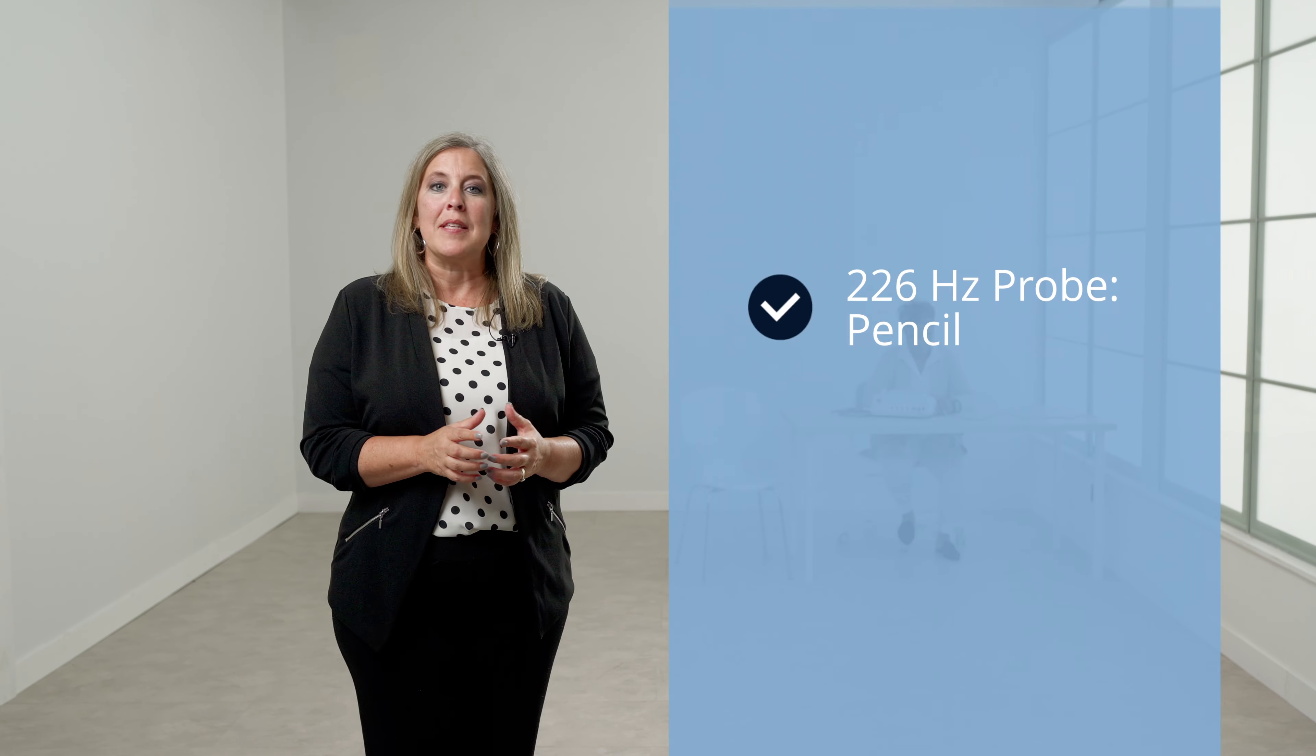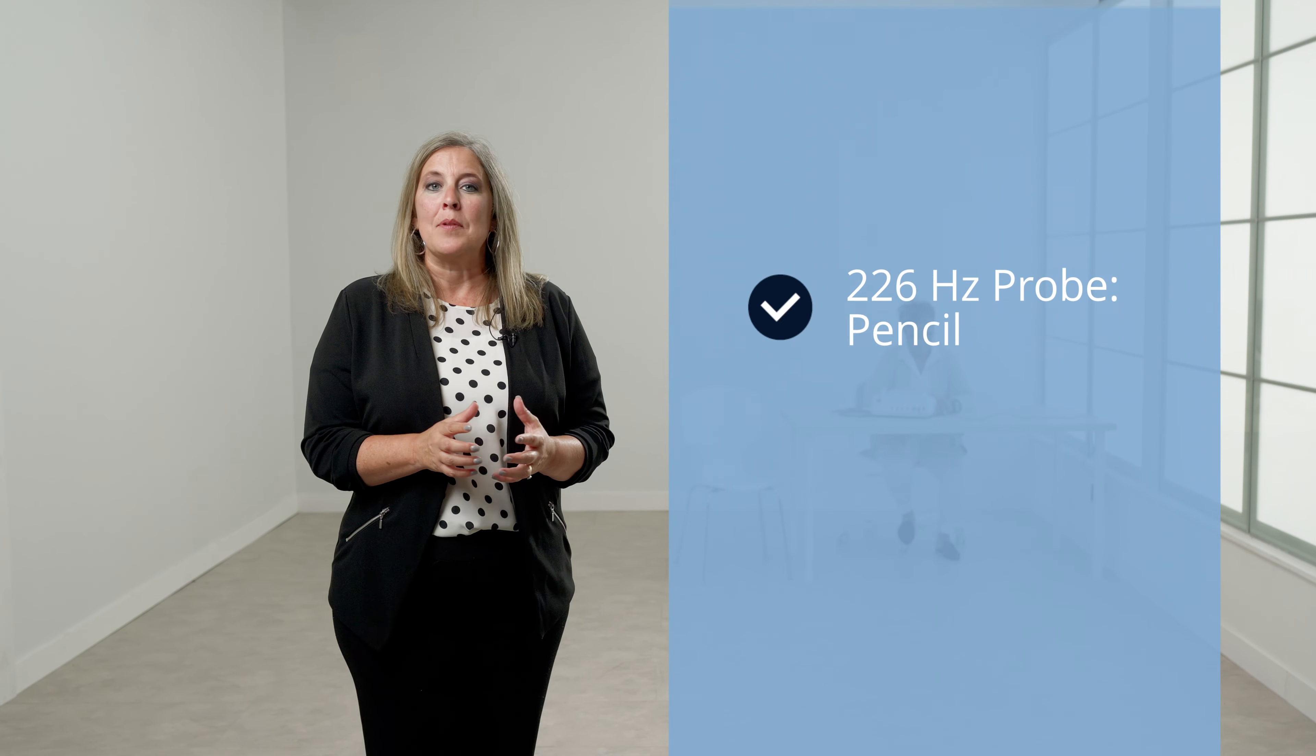There are two probe types for tympanometry. The 226 Hz probe is the standard probe and resembles a pencil. A combination probe with a shoulder mount will be provided for a version that includes a 1000 Hz probe tone.